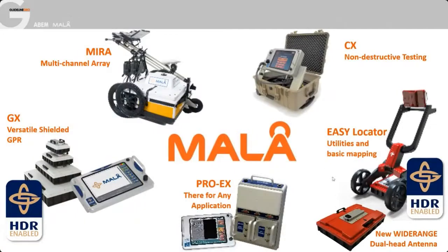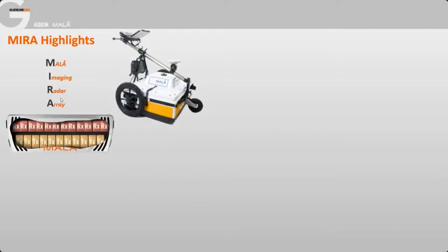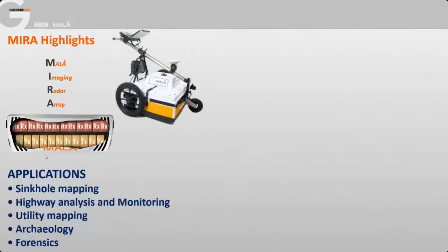And as I say, at the heart of the ProX is our original MIRA system. MIRA stands for MALÅ Imaging Radar Array. This is where we have a large number of transmitter and receiver units in a single box that allows us to collect data in a very dense pattern, and that allows us to pick out incredible detail in the results.